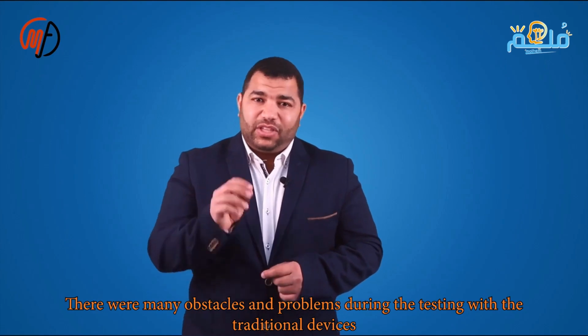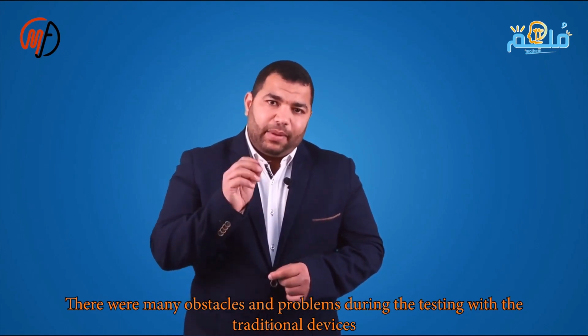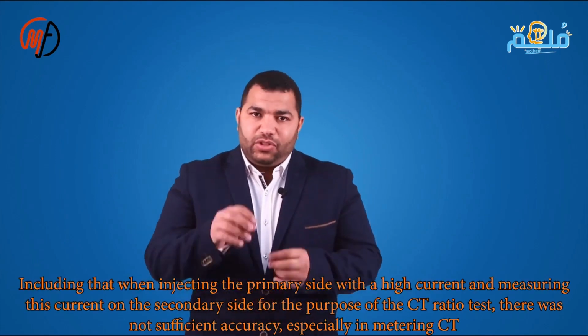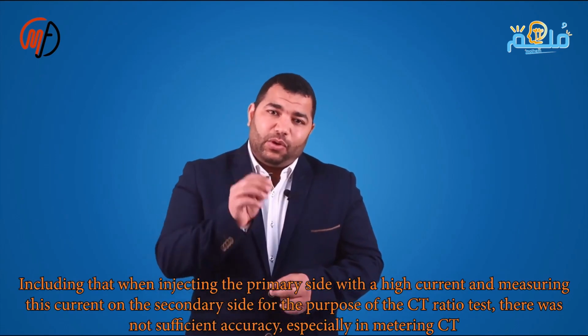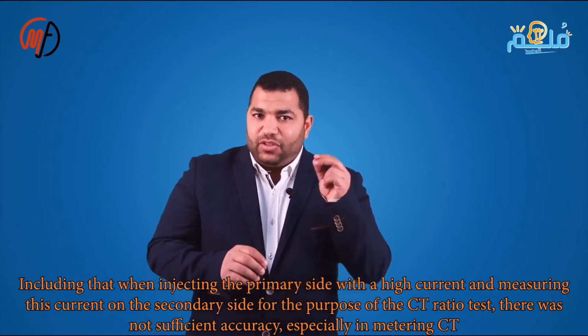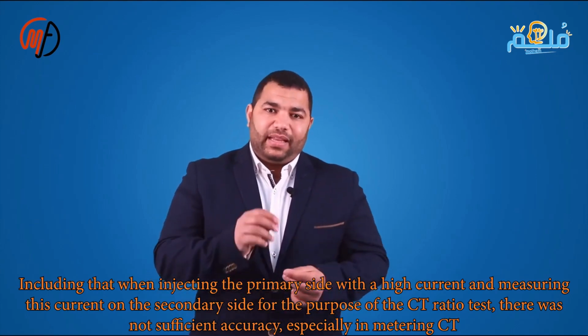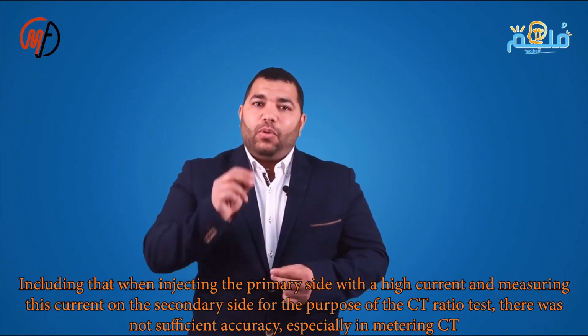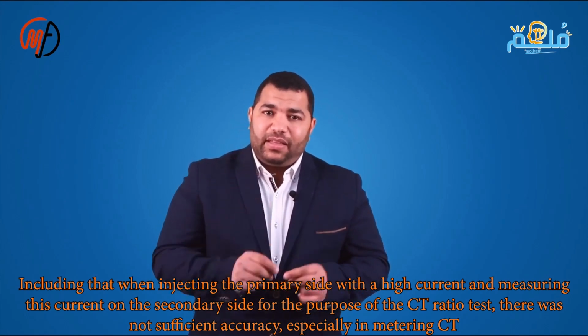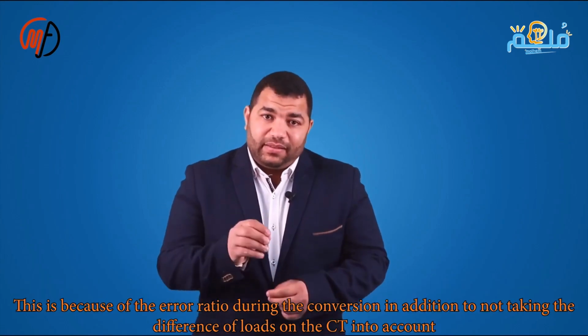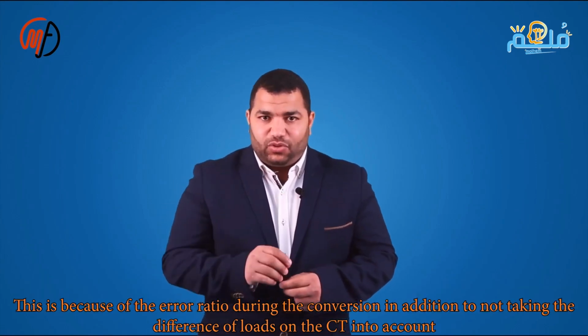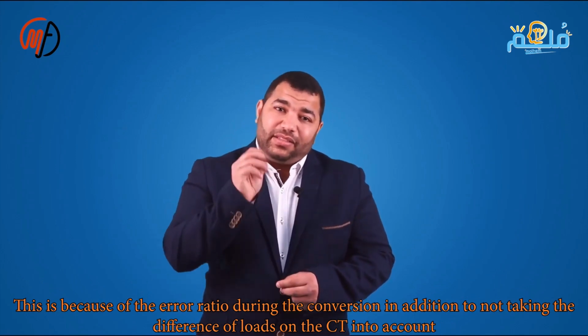For instance, when injecting high current on the primary side and measuring this current on the secondary side, while checking the CT ratio, there wasn't enough accuracy, especially in metering CTs, due to the error rate during conversion and not accounting for load variations. Another issue is when applying a variable load for testing. In some cases, especially when the value is high, it can be enough to damage the CT during the test, leading to a report stating that this CT is faulty.